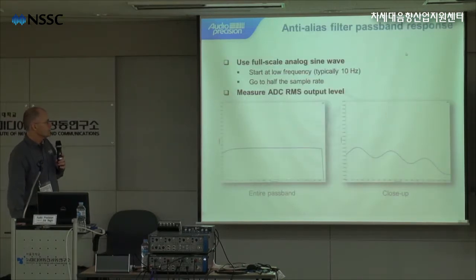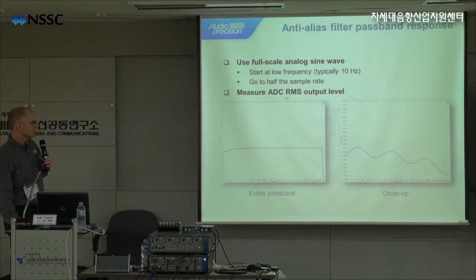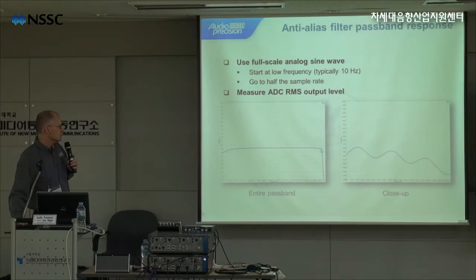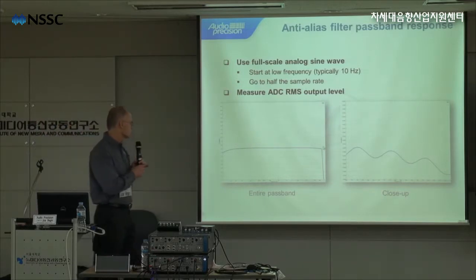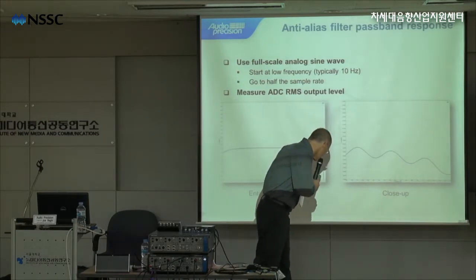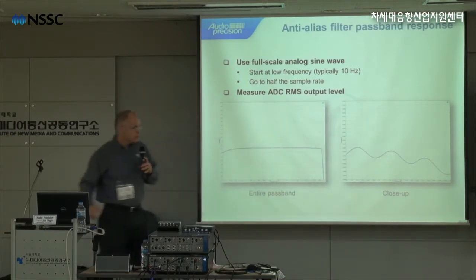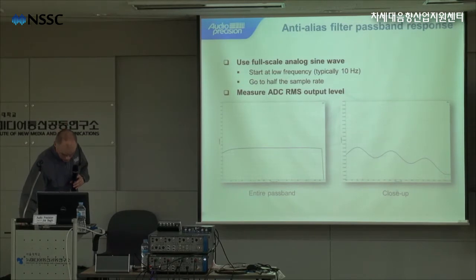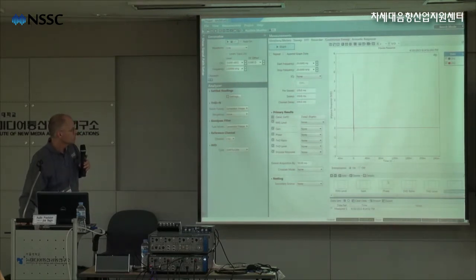So for anti-aliasing filter passband response, you want to use a full-scale analog sine wave, start at a low frequency, typically 10 hertz, and go to half the sample rate, and measure the A to D converter RMS output level. So this shows the entire passband, and there's a close-up here. It's hard to tell the resolution on this monitor, but we can look back in the software at the measurement that we just did.